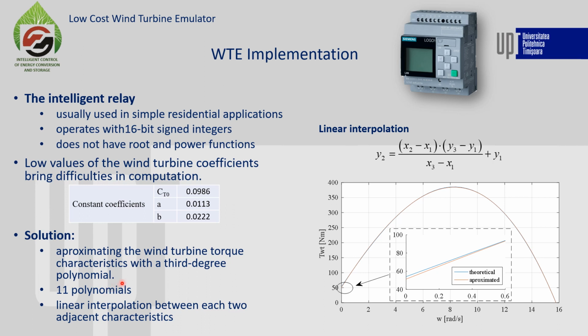Okay, but the wind speed doesn't jump directly from 5 meters per second to 6 meters per second, or from 3 meters per second to 4 meters per second. There are also values between the characteristics. So to overcome this problem, linear interpolation between each two adjacent characteristics has been done, and it has been found that this method offers a very good precision for the minimum number of 11 characteristics.